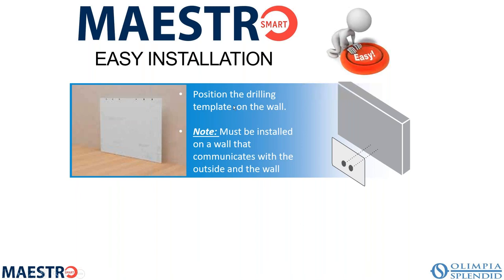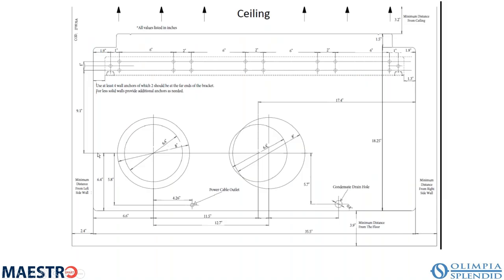So the first thing you do is you position the drilling template on the wall. So this is a 36 inch by 24 inch heavy duty piece of paper that gets mounted on the wall where you want your unit to be, okay? And again, it must be a wall that communicates with the outside. So there's a look at the template that ships with the unit. Now, the thing to keep in mind here is you see an 8-inch hole here, right? An 8-inch hole here, and then you have the same thing over here. So you require 2 8-inch holes in the wall, and they have to both be 8-inch.